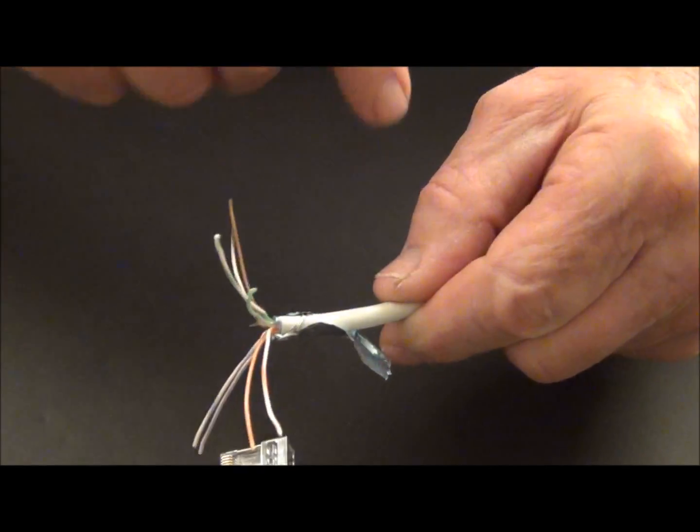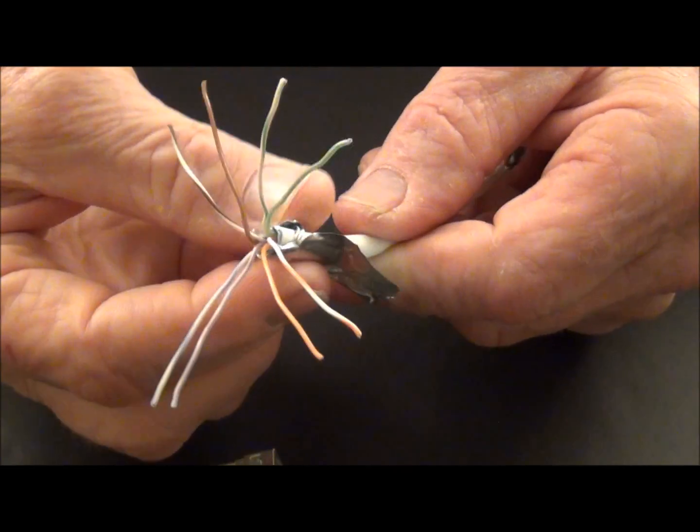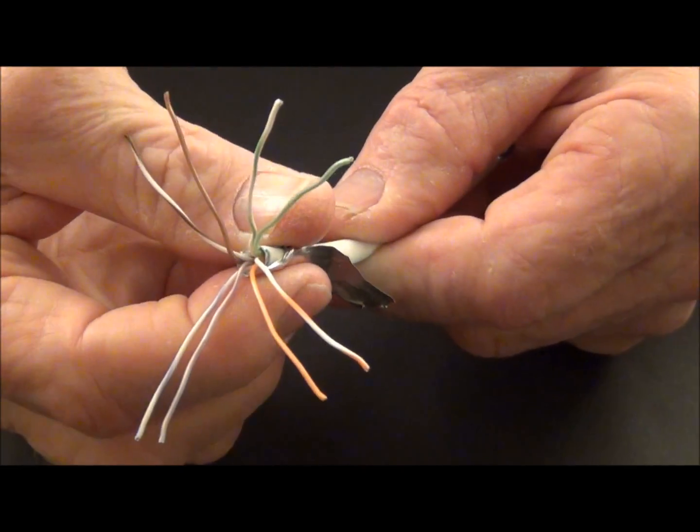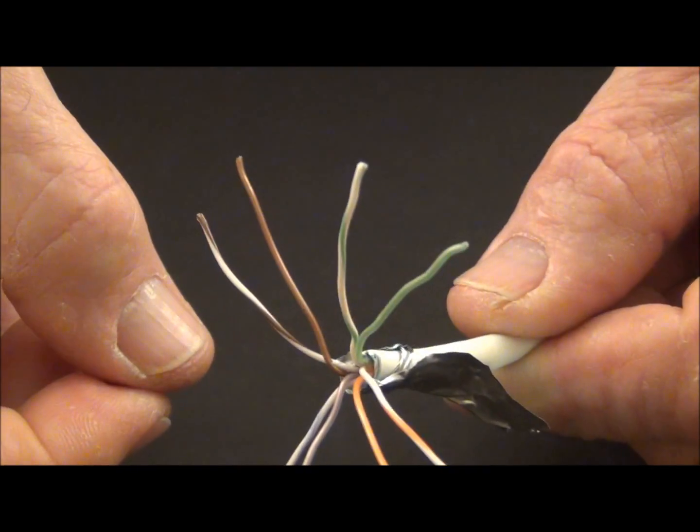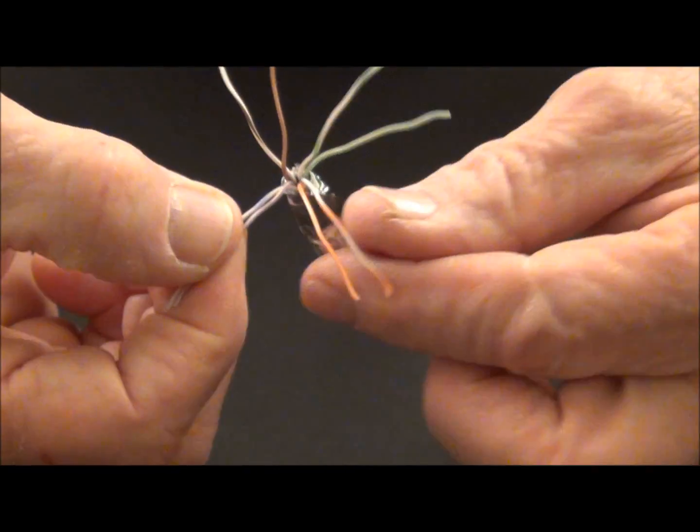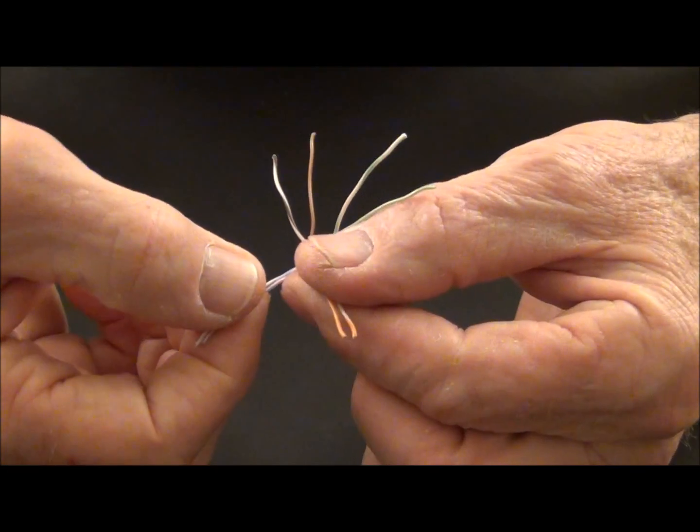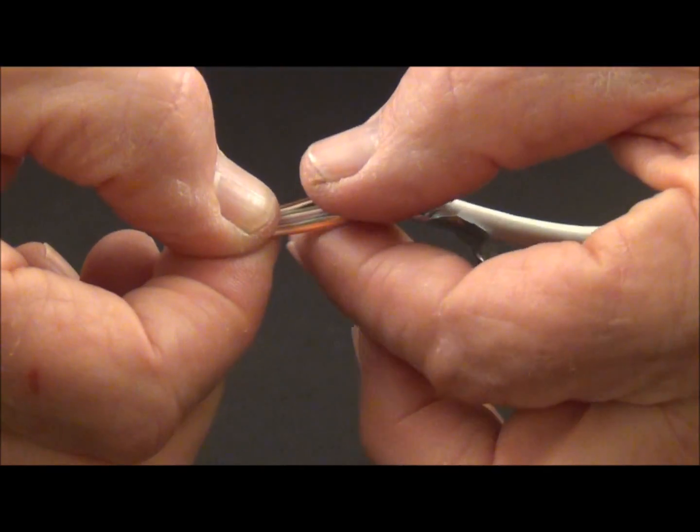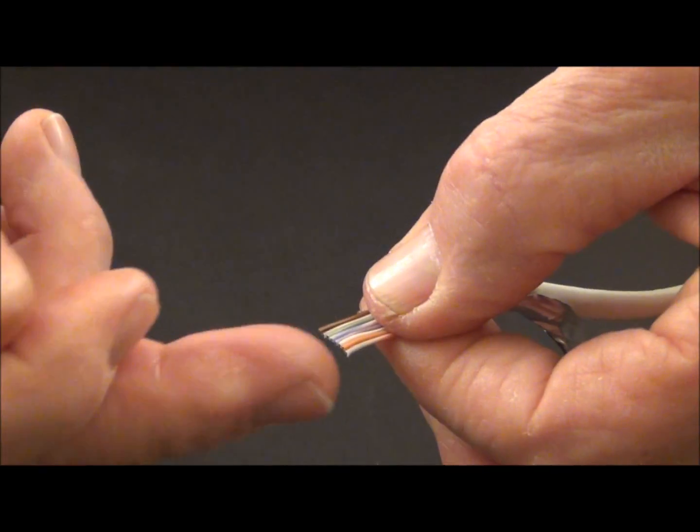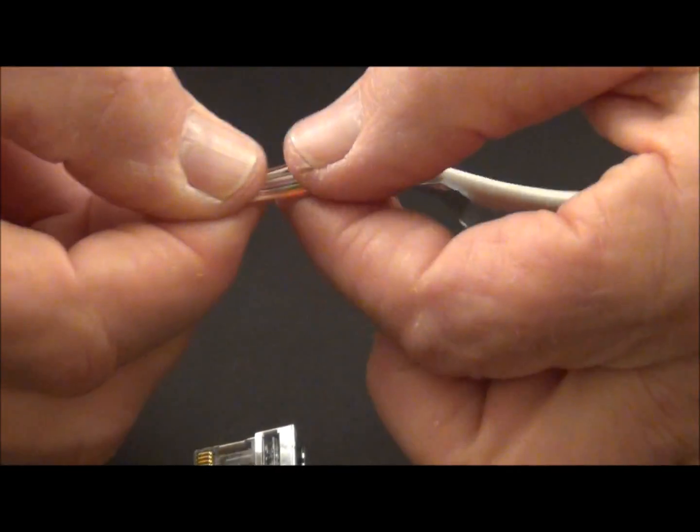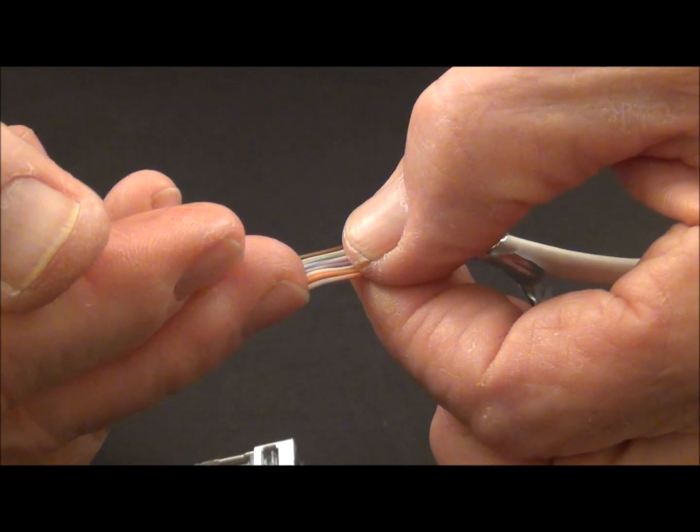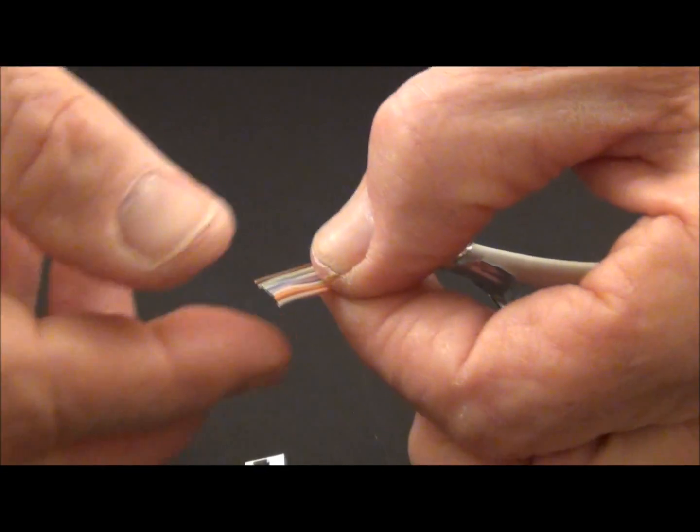So I'm going to go ahead and just sort of prep the foil right there. I've taken my drain wire, it's wrapped around the bottom of the jacket, between the jacket and the foil. And then we're going to lay these out and into the pairing. Now my pairs are laid out to the configuration of the B, orange-white first and so forth.